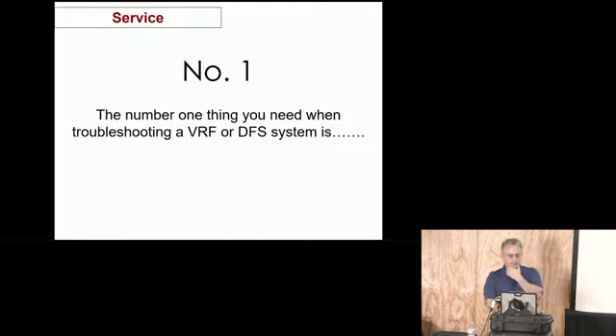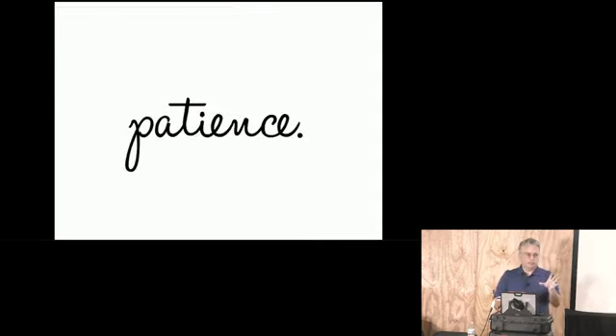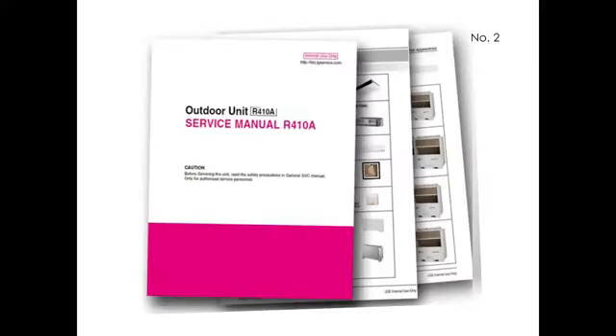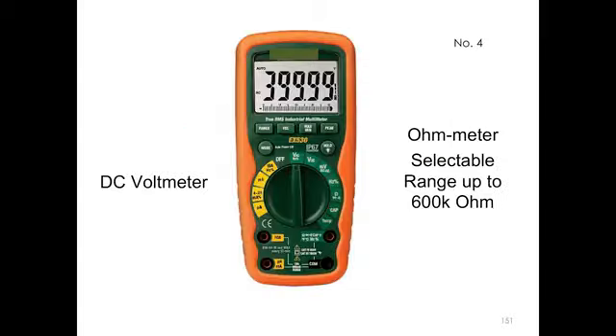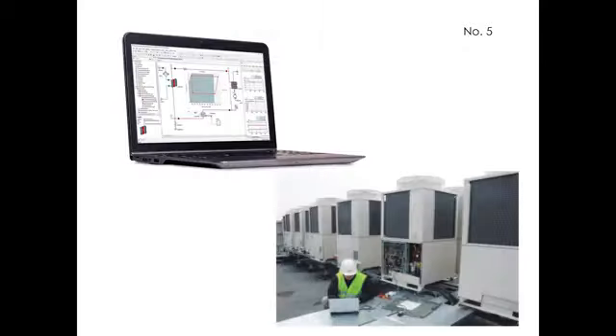So the number one thing that you should remember about service, the most important thing when you are approaching a system, is you have to have patience. All right? If you've never worked on these systems before, and you think it's going to take an hour, schedule 3. Also, get the manuals. The manuals are your key roadmap. You're going to need a DC voltmeter with 600K ohms. If you're working on VRF, you're going to need a computer because you're going to be interfacing with the computer.